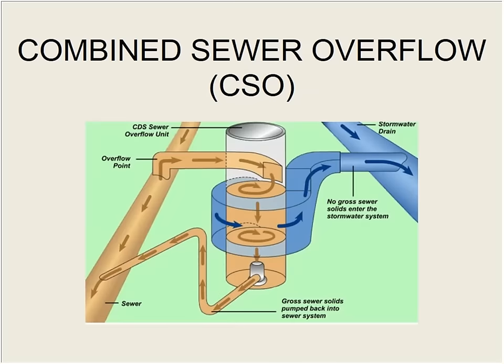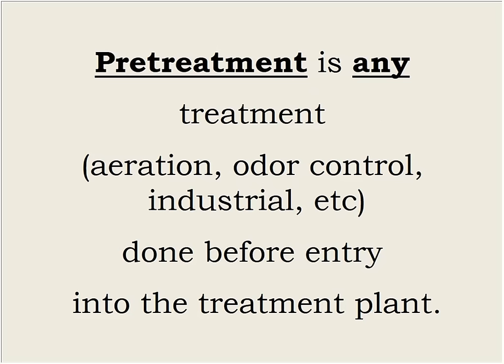And now this is showing you one that's set up with a cyclone system so that it takes out the grit. It may also get disinfected before it actually discharges out into the system. So we use the term pre-treatment. Pre-treatment is any treatment that's done to wastewater outside the confines of the POTW. If the city is dosing lift stations with sodium hypochlorite or potassium permanganate to keep odors down, that's technically pre-treatment.